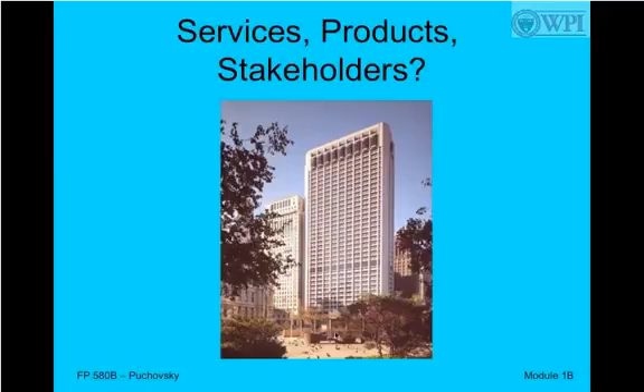As a result, 3 firefighters died in this particular fire. Also, the fire spread up to about the 23rd floor, where it did finally reach a sprinkler system, which helped contain the fire. Throughout the course of the fire, they were able to locate these devices that could be used to adjust the pressure-reducing device, okay, which would then allow a sufficient amount of flow. Prior to that, the fire department was running their hoses manually up 17 flights of stairs to these fire floors, okay, which took some delay, and unfortunately resulted in the fatality of 3 firefighters.